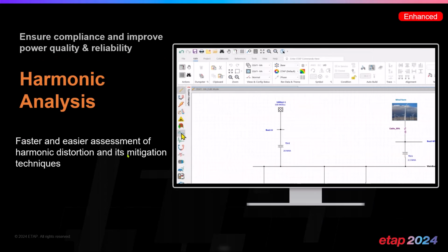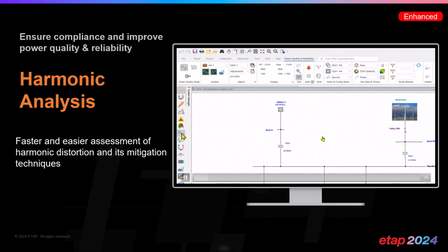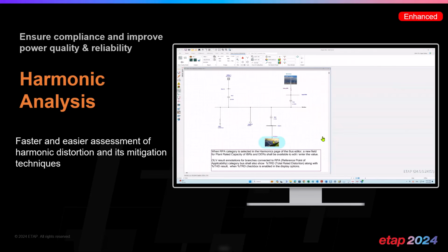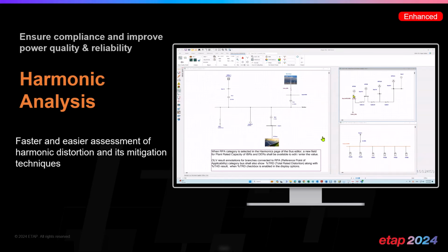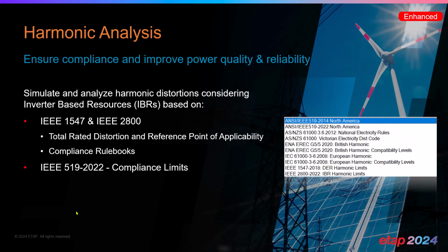The ETAP Harmonic or Power Quality Assessment Group allows you to perform faster and easier assessment of harmonic distortion and its mitigation techniques using various components that are already available within ETAP, including all the power electronic devices, including inverter-based resources. Within harmonic analysis, we've of course enhanced the program to now include rule books associated with IEEE 1547 as well as IEEE 2800 that include the total rated distortion as well as the reference point of applicability. And these rules are now added to the existing rule books that we have for harmonic evaluation, including Australian standards, British standards, European standards, and of course, North American standards.